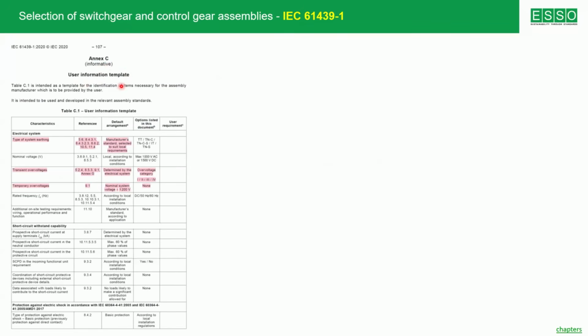Ideally, the user or the consultant on behalf of the user should be able to fill up the form, the annexure C, and give this information to the panel board manufacturer, so that he can make it according to your requirement. Now, here are the subjects of earthing. The first one, starting with the type of system earthing, which is explained in the standard clause number 5.6, 8.4.3.1, 8.4.3.2.3. Multiple clauses, the requirements are explained. So basically, the consultant who is designing the installation must fill up this particular format, and this is going to be the requirement of the client for making the panel board, switchgear, control gear assembly as per 61439.